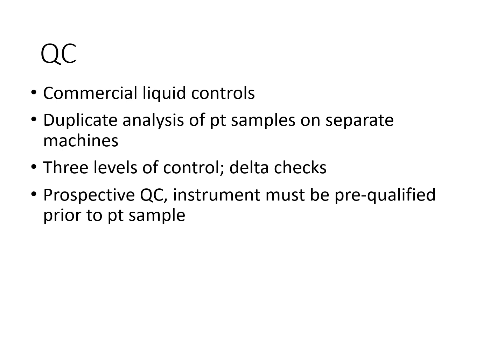Quality control: there are commercial liquid controls that are already prepared for routine quality control. These controls have known values to ensure the instrument accuracy. We're going to perform duplicate analysis of patient samples on separate machines. This can help verify consistency and reliability across instruments.